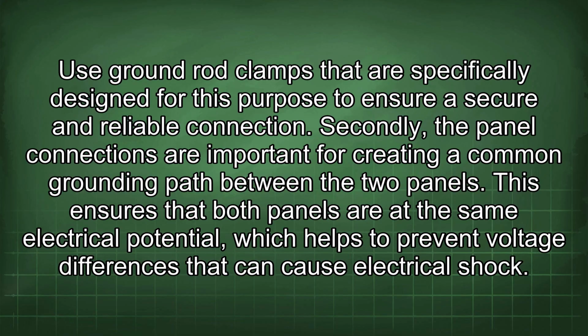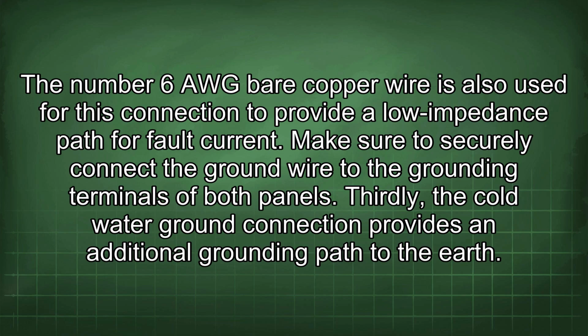Secondly, the panel connections are important for creating a common grounding path between the two panels. This ensures that both panels are at the same electrical potential, which helps to prevent voltage differences that can cause electrical shock. The number 6 AWG bare copper wire is also used for this connection to provide a low impedance path for fault current. Make sure to securely connect the ground wire to the grounding terminals of both panels.